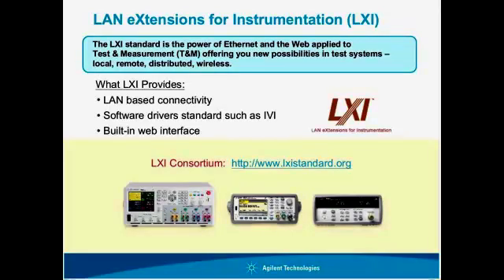Besides just LAN connectivity, the LXI standard also defines that certain drivers have to be installed on an instrument, such as IVI drivers. It also requires the instrument to have a built-in web interface, so I can access the instrument's network settings, and in some cases, depending on the instrument, the instrument's actual controls — with a web browser remotely using an Ethernet network, without any special software, just a web browser.